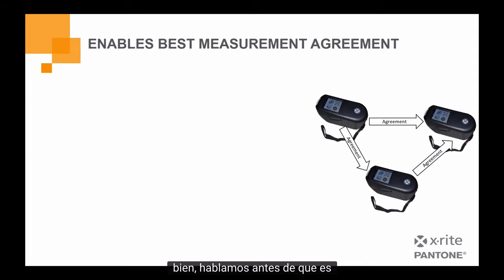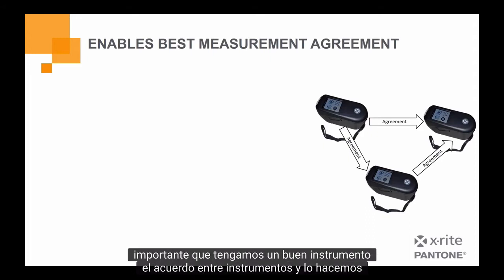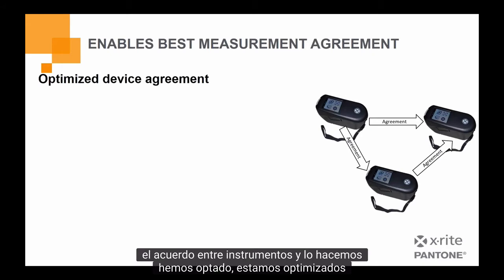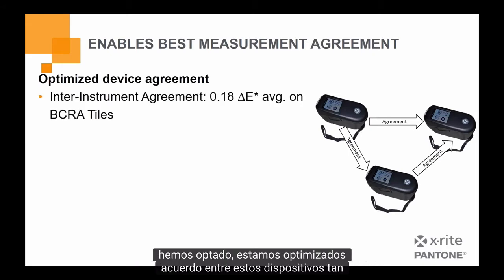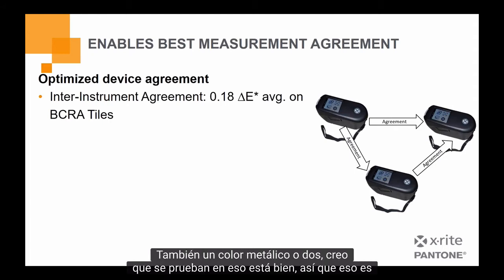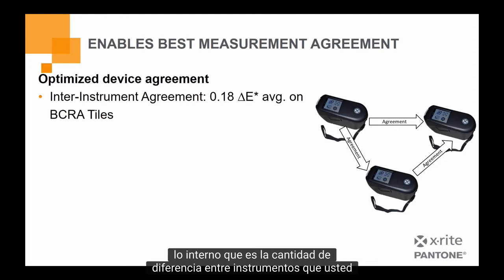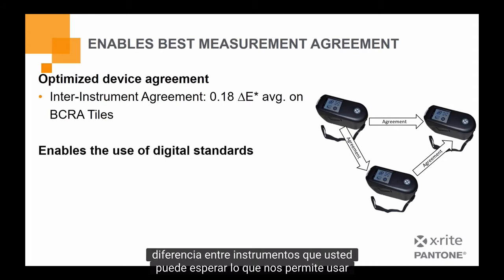Okay, we talked earlier about how it's important that we have good inter-instrument agreement, and we do. We've got optimized agreement between these devices. So between multiple MA-5 QC instruments, we're talking about a 0.18 delta E average on BCRA tiles. There's also a metallic color or two, I believe, that are tested in that. So that's the amount of difference between instruments that you can expect, which enables us to use digital standards.